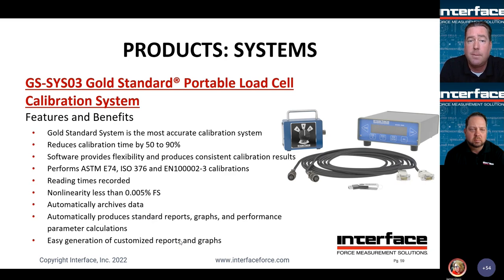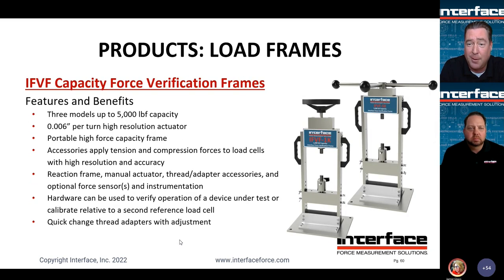Much like the E4 system, the 9840 functions as the A to D. The software is where you upload your standard calibration data and generate set point files. And then again, just to touch on it, as with the E4 calibration software, it automatically generates reports, graphs, and performance that are customizable to your specific requirements. And again, primarily the time savings we see there is on the report generation side.